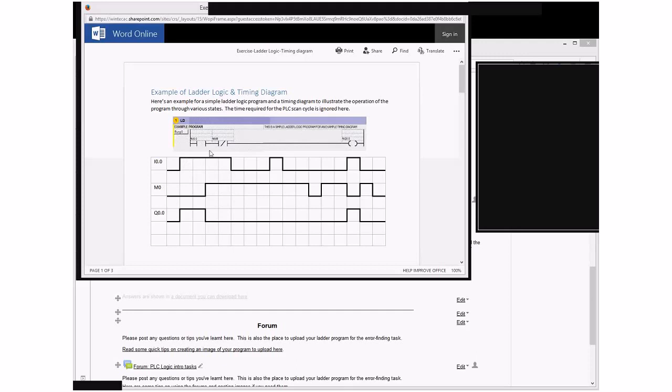So one of the tricks with this one is in our program we have M0 being a normally closed contact which means the logic for that part turns on when that memory location or memory address is in a low state.